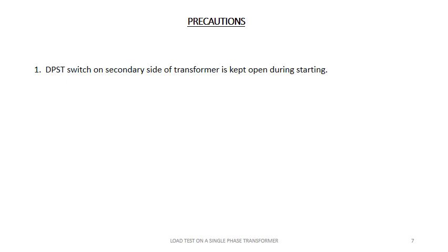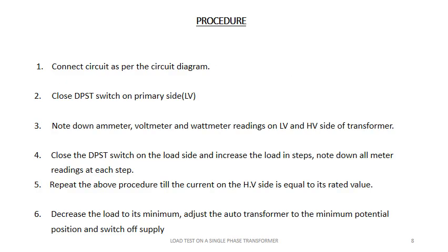Before going to the experiment, some precautions should be taken: the DPST switch on the secondary side of the transformer is kept open during the starting procedure. Connections are made as per the circuit diagram. Close the DPST switch on the primary side. Note down the ammeter, voltmeter, and wattmeter readings on the LV and HV side. Close the DPST switch on the load side and increase the load in steps. Note down all meter readings at each step. Repeat the procedure until the current on the HV side equals the rated value. Decrease the load to minimum. Adjust the autotransformer to the minimum potential position and switch off the supply.